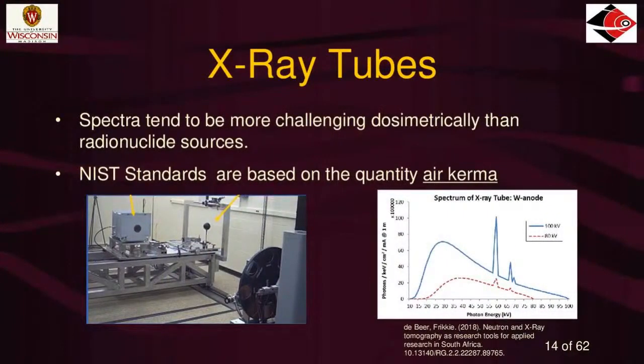The dosimetry of X-ray tubes is different from iridium-192. Spectra tend to be more challenging dosimetrically than radionuclide sources. Radionuclide sources have the same energy lines coming out of each one — the same gamma rays. But X-ray tubes are a little more challenging because they could be slightly different every day. The standards for X-ray tubes are based on air kerma, not air kerma strength as used for iridium.